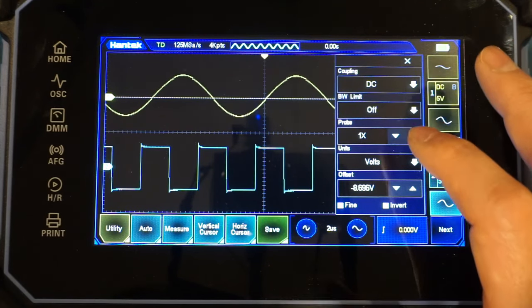And here I'm using an avalanche pulse generator to generate a very short and fast rising pulse. And you can see the measured rise time is right around 1.7-1.8 nanoseconds. Like I mentioned before, in my opinion, the best way to measure the analog bandwidth of an oscilloscope is through the use of an avalanche pulse generator. And here you can see the measured rise time is right around 1.7 nanoseconds. And that actually translates to just above 200 MHz of bandwidth, which means that the claimed bandwidth is accurate.